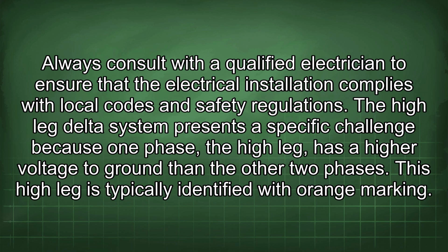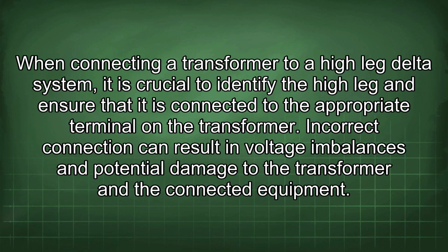The high-leg delta system presents a specific challenge because one phase, the high leg, has a higher voltage to ground than the other two phases. This high leg is typically identified with orange marking. When connecting a transformer to a high-leg delta system, it is crucial to identify the high leg and ensure that it is connected to the appropriate terminal on the transformer. Incorrect connection can result in voltage imbalances and potential damage to the transformer and the connected equipment.